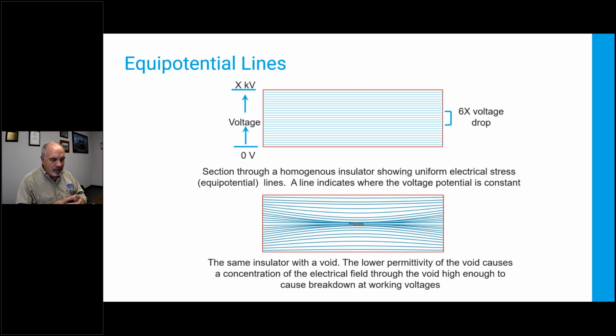That insulation might collapse for a variety of reasons, right? It might not be able to withstand the field applied to it because it's just designed wrong, it's dirty, whatever. But what happens is when you have an area of different permittivity, so a void has different permittivity than XLPE, and a dirty insulator covered with humidity-laden dust has a different permittivity than the ceramic insulator base. That causes a concentration of field. So you actually get a higher voltage across the field than you would if everything was homogeneous. And that just makes it that much worse. And that causes your breakdown. And once it breaks down, then you've increased the stress on the rest of the insulation.